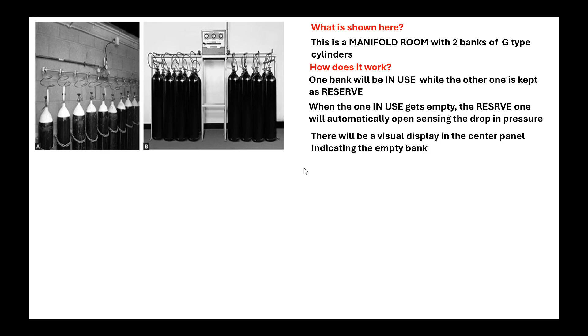And there is a central panel here which will show what is the pressure in bank A and bank B. And if there is an empty cylinder here, it will give an alarm, as well as a visual display. A red light will burn saying that bank A is empty, and immediately the technician will come and remove all the empty cylinders and fit the new cylinders. Okay. So one bank will be in use while the other bank is kept in reserve. When the one in use gets empty, the reserve one will automatically open because low pressure here will automatically allow this gas to come out from the full cylinder. So that is the sensing mechanism. And there will be a visual display in the central panel. This is the central panel indicating the empty bank, and we have to replace all the cylinders. And this is the panel in a close view to see what is the pressure and how the connections are made.